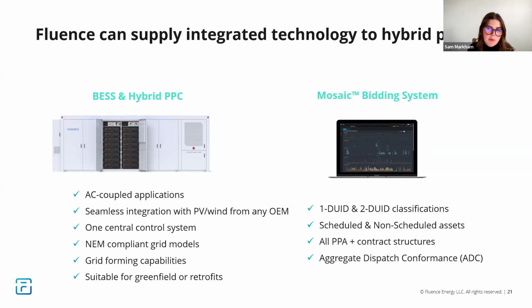It really depends on how much you're looking to charge. Obviously, you can't charge a BESS more than it's capable of charging in a short period of time. But you could potentially split between what's coming from your co-located PV or wind and what's coming from the grid. The caveat is that with DC coupling, there can be certain modes those assets operate under, which could mean that at certain times the asset is limited to charging just from the co-located asset or just from the grid. So the example given works from an AC coupling perspective, but could be limited from a DC coupling perspective.